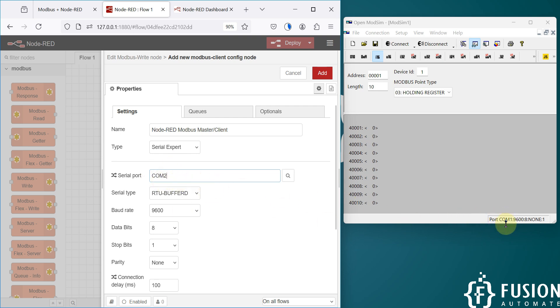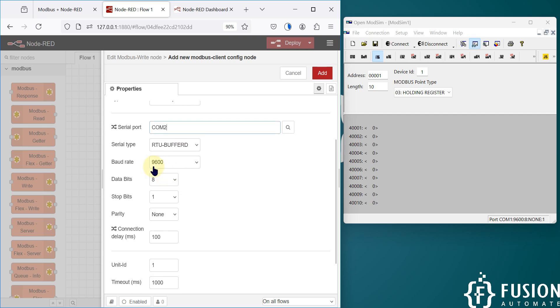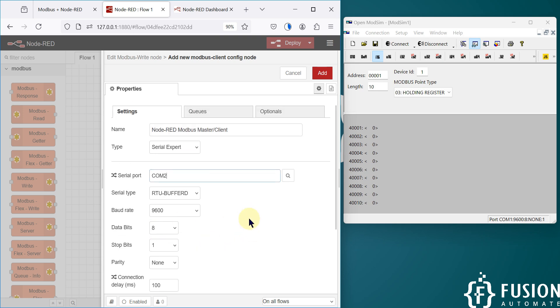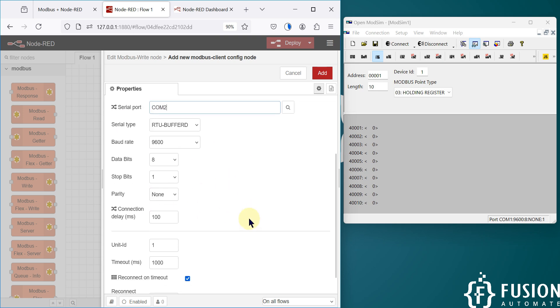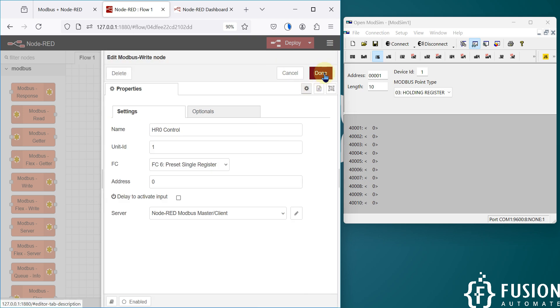We can't use a single COM port multiple times, which is why we use COM2. The serial type is RTU, baud rate is 9600, data bits 8, stop bit 1, parity none. That's all you need to configure — click the Add button and press done.